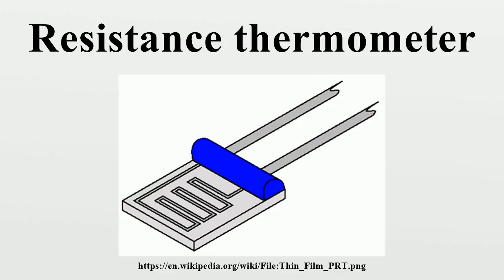Wiring configurations. Two-wire configuration. The simplest resistance thermometer configuration uses 2 wires. It is only used when high accuracy is not required, as the resistance of the connecting wires is added to that of the sensor, leading to errors of measurement. This configuration allows use of 100 meters of cable. This applies equally to balance bridge and fixed bridge system.